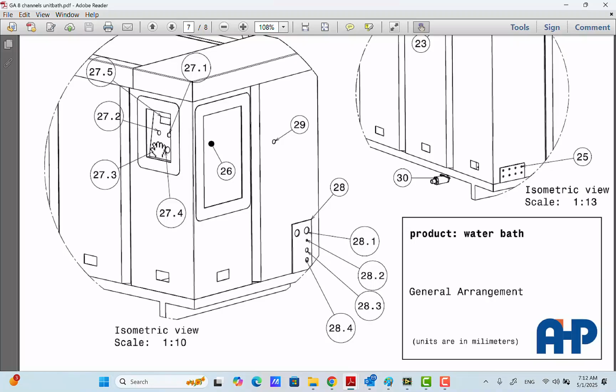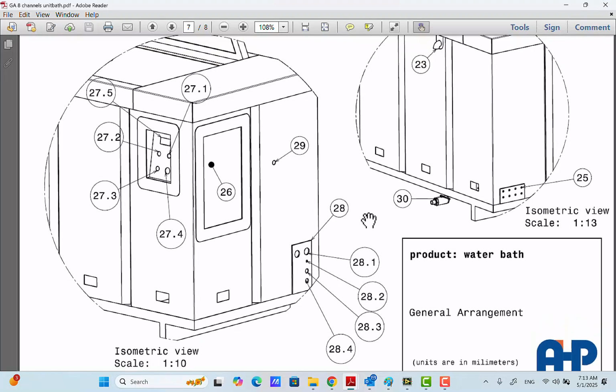Here on the panel, you have another key for the auxiliary heater. For example, if you have one or two auxiliary heaters, you will have one or two keys here with the writing of heater 2 or heater 3. Suppose that you want to raise the temperature of the tank to 80 degrees from the room temperature, which is 25, for example. You want to increase the temperature rapidly. You can use auxiliary heaters. You can turn these auxiliary heaters on to raise the temperature rapidly.